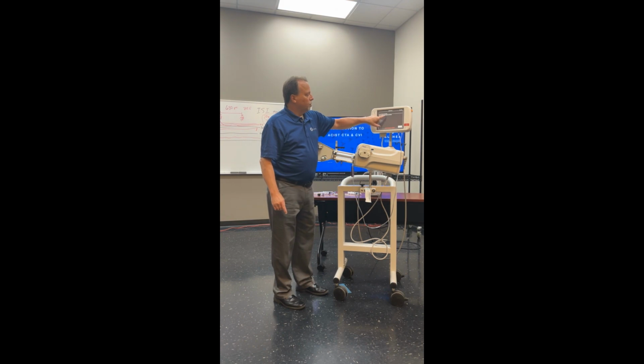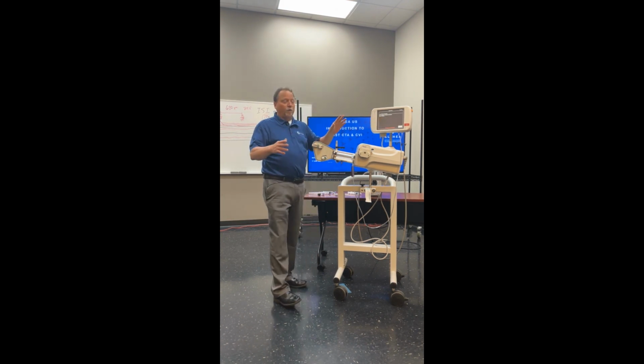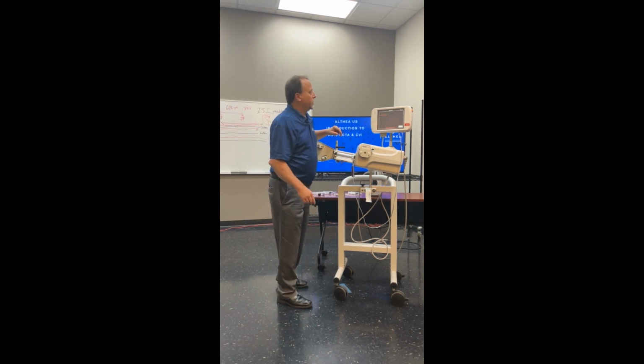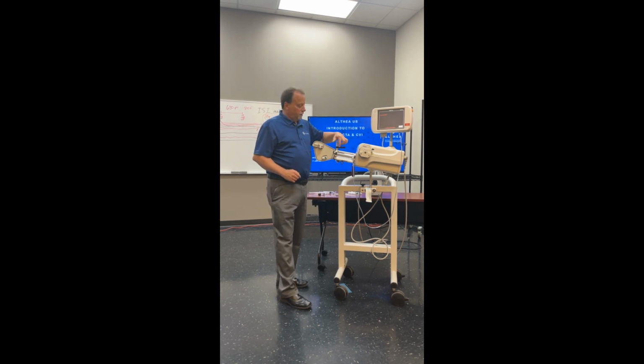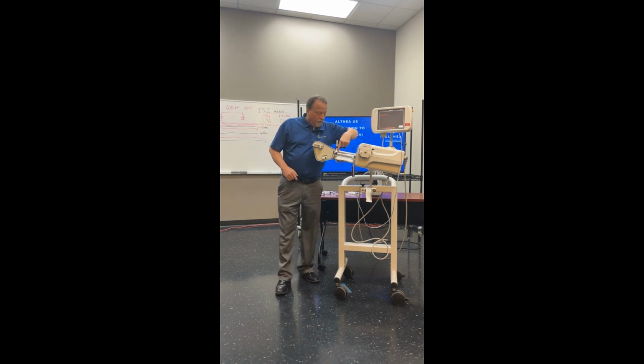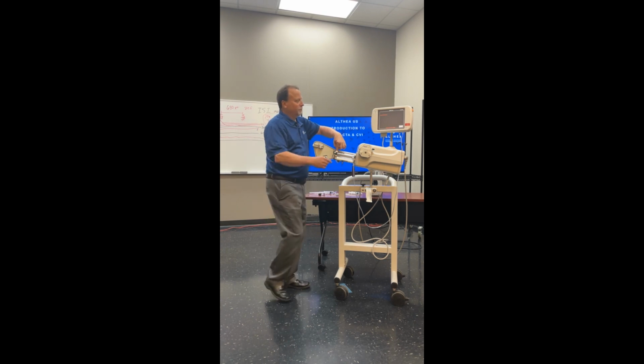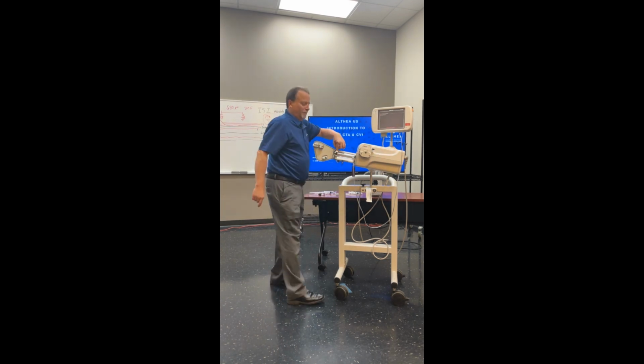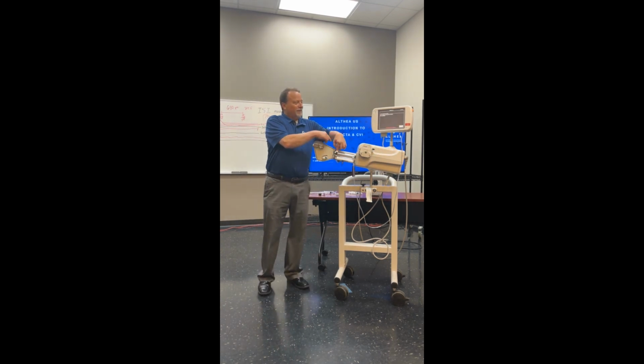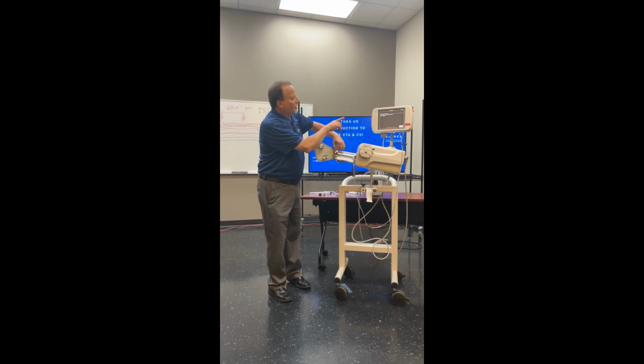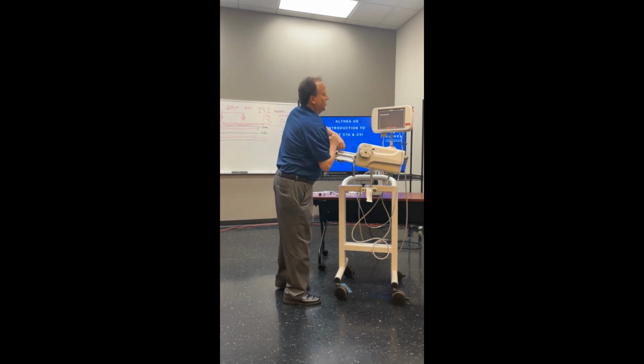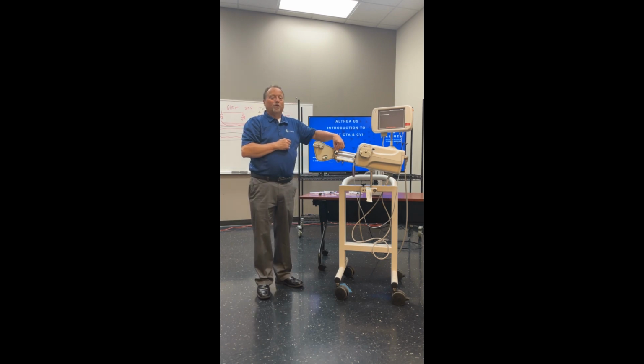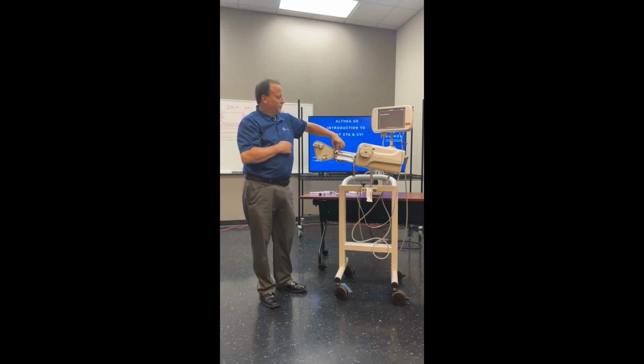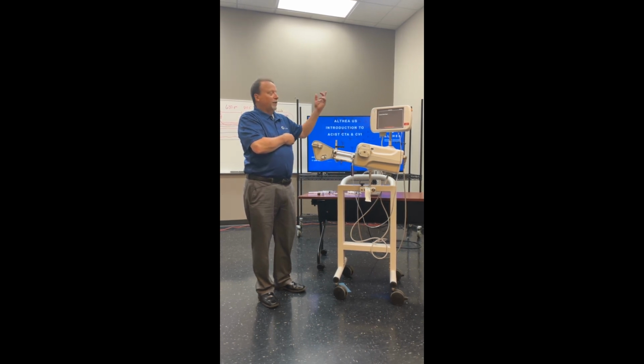So it tells me to load the syringe assembly. I'm not going to. I hit done. It says syringe not detected. I put my finger in the syringe sensor and hit OK. The sensor sees that it is closed, and now it's going to engage the syringe plunger, which is just my finger. And the piston is going to run forward, is going to advance. And now I can take my finger out.